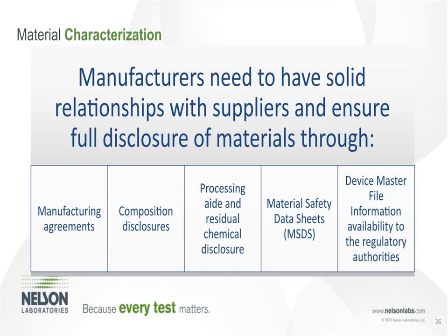We have manufacturing agreements. Most of the time a manufacturing agreement is a "do not change anything unless you tell us" kind of agreement. Be careful with those. We had an example a couple years ago where we were doing routine cytotox testing on a glass material that they purchased and were using in their device. So they did a raw material cytotoxicity on every lot. And for years they got zeros. And all of a sudden they started getting 2s. Now, 2s in cytotoxicity is still a passing result, but man, you go from 0s to 2, what's going on?